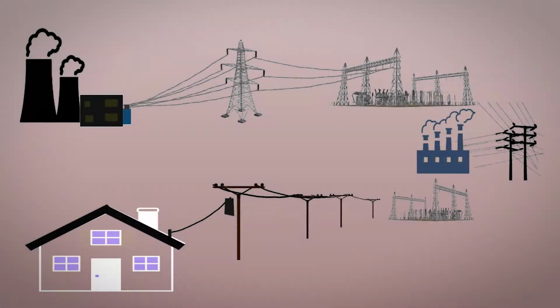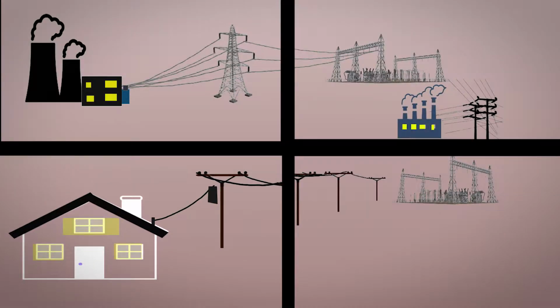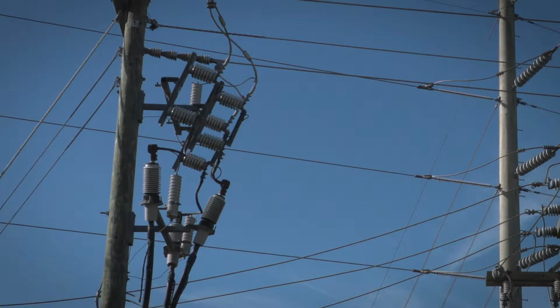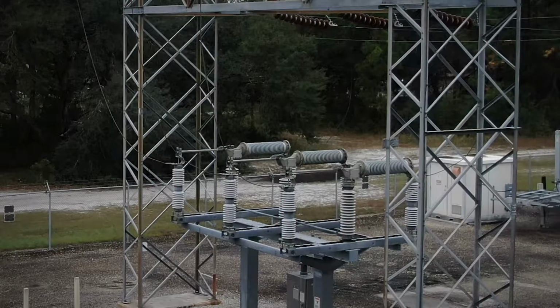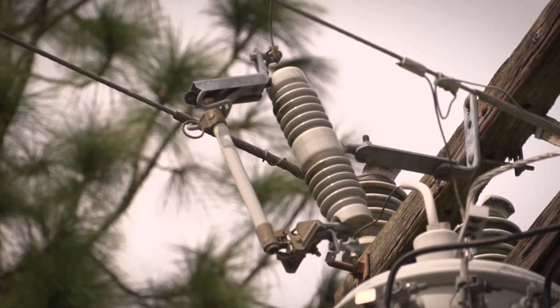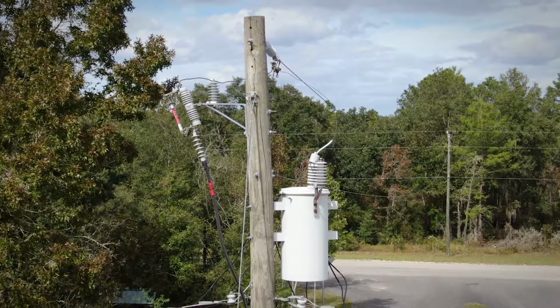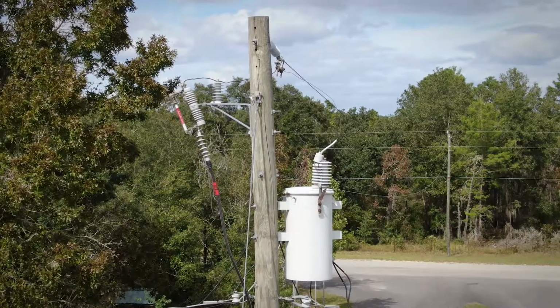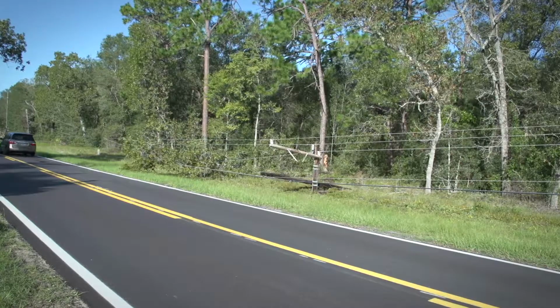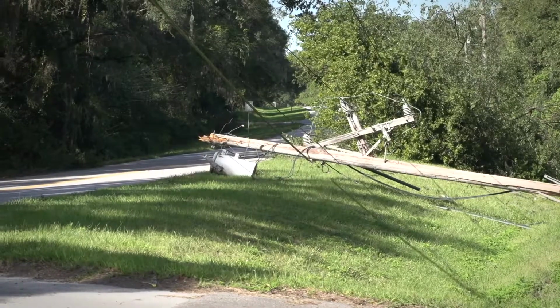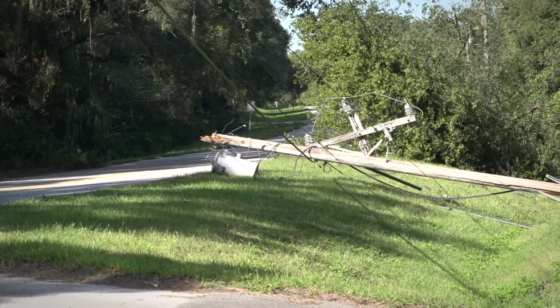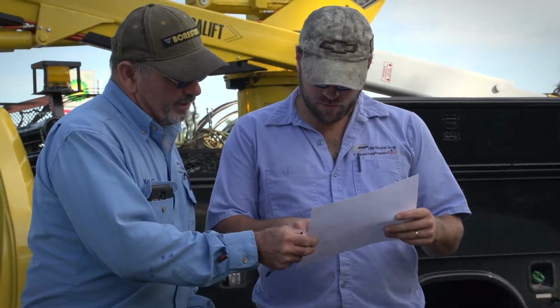To minimize the effects of any power disruption, all electric utilities divide their distribution system up into sections, with each section overseen by a series of protective devices. Whether the devices are breakers, reclosers, or fuses, their main function is to isolate the faulted area from the rest of the system when a problem occurs, thus reducing the number of people affected by the fault, damage to equipment in the area of the fault, and the time it takes to locate and repair the problem.